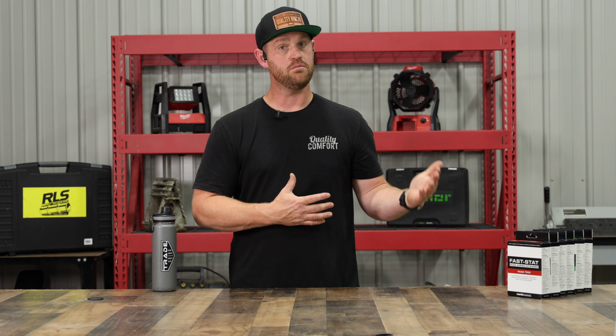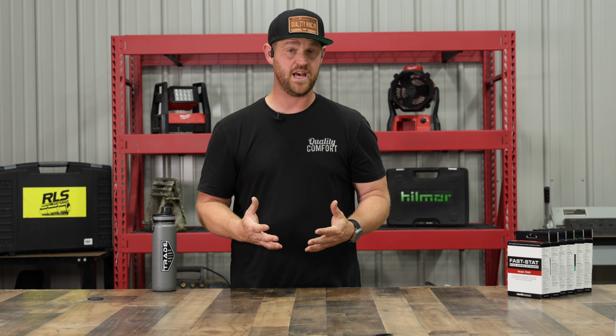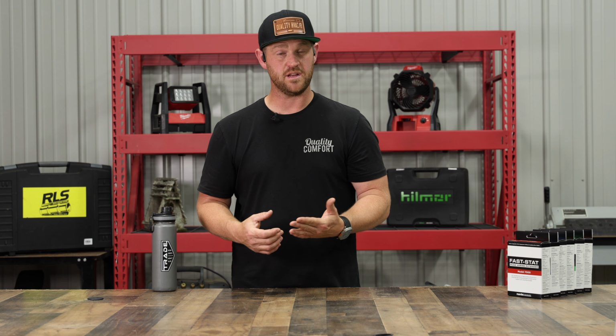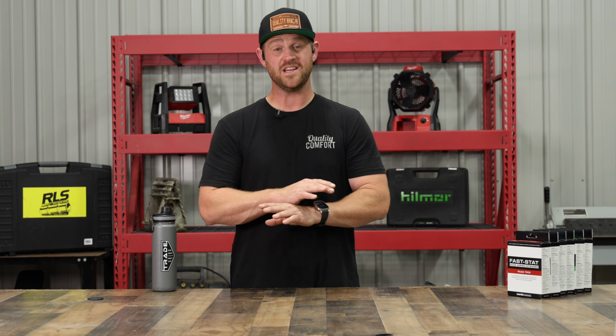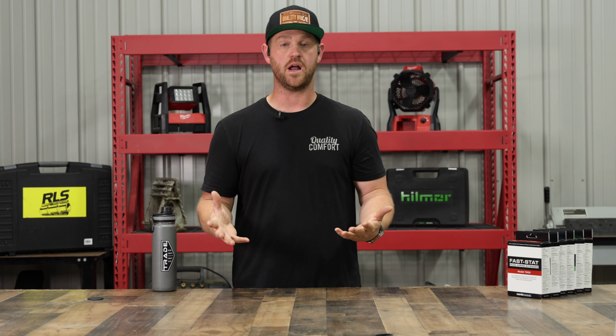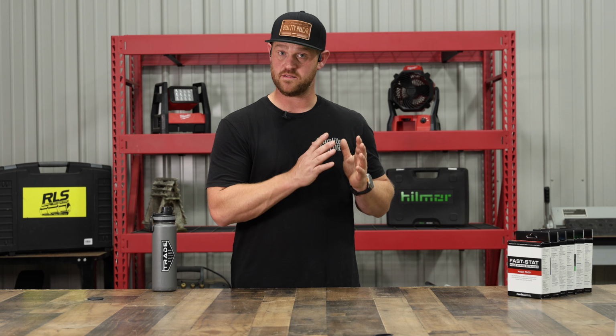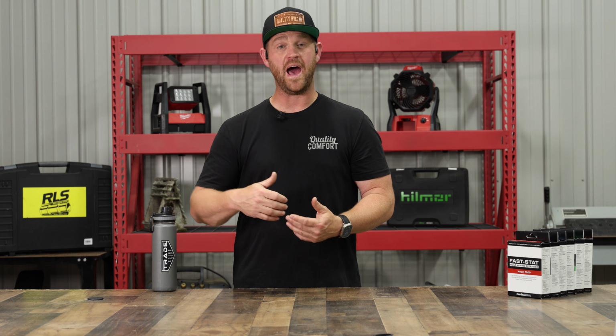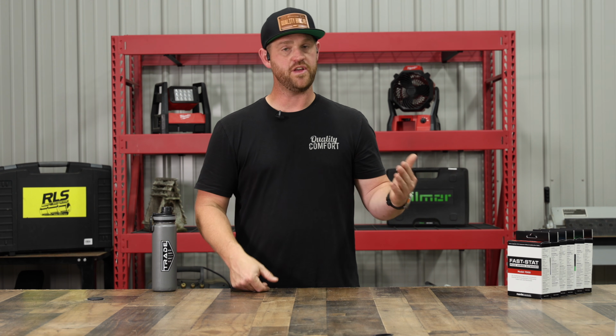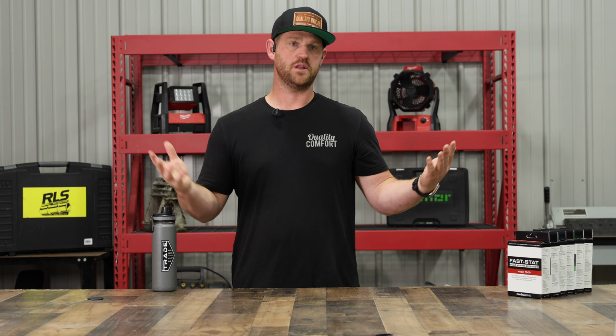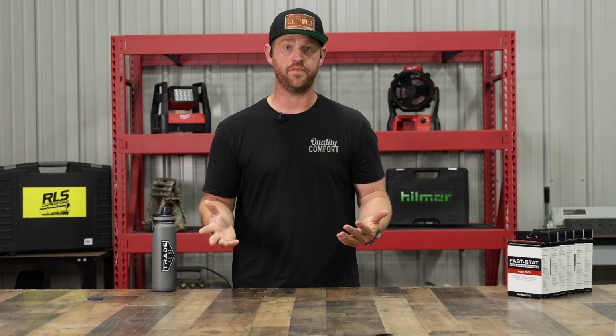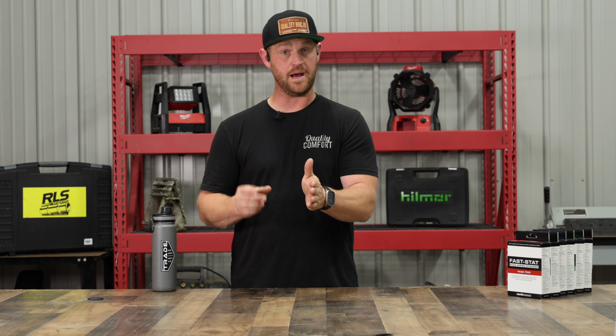So again, if it's not 95 degrees outside, more than likely whatever unit you have, if it's single stage, it'll be oversized. The reason is that we size the equipment, and this is a standard, for basically the hottest day of the year, so that it can keep up. But we don't have the hottest day of the year every single day, so the equipment is going to be oversized, let's say 80% of the time. I'm just throwing a number out there. That's where two-stage and variable speed equipment really shine, because they can adapt a little bit. The two-stage can adapt a little bit, and variable speed can adapt a lot to your environment.